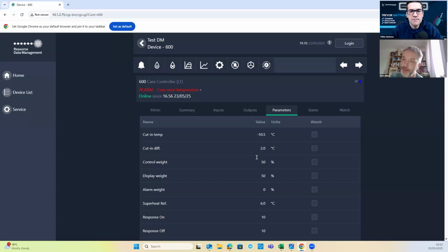because you want to read the warm part, right? You want to read the air coming back out of the room. The only time I would deviate from that on a cold store is if you've got, let's say, a dual discharge cooler in a teeny room and you've got a really bad situation with air bouncing around the room. It does happen. Certain customers have little tiny prep rooms, for example, and if you just did it by air on, it would not reflect what the room's doing, because the air off influences it quite a lot more in a small room. So you might need to fiddle with that.